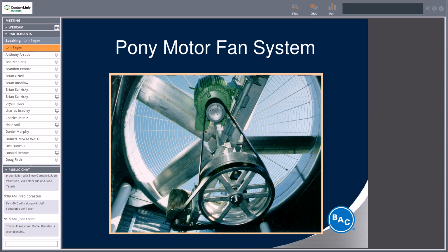Pony motor fan systems, you may run into these. This was, years ago, the poor man's VFD, where we would put on a pony motor that was about a third of the main fan motor, so that if you had reduced capacities during the year, that tower could run off a smaller motor, and again, reducing capacity, or reducing the cost to operate.